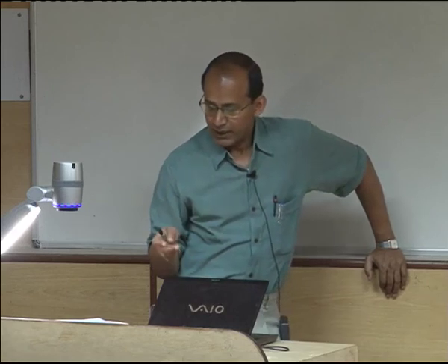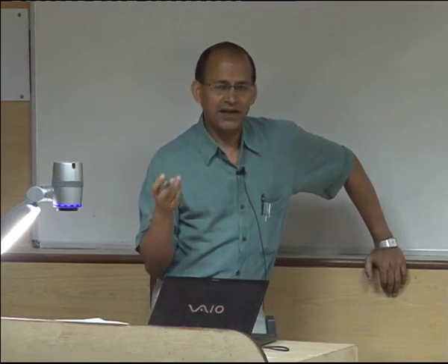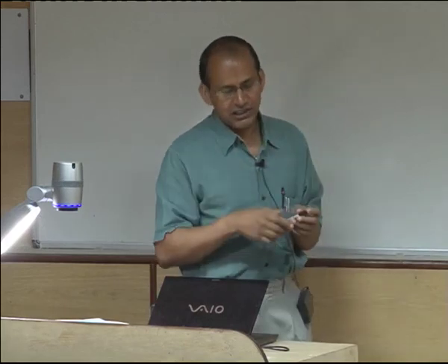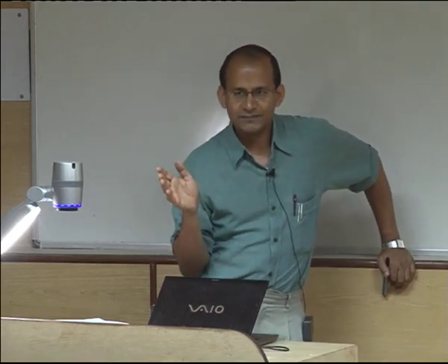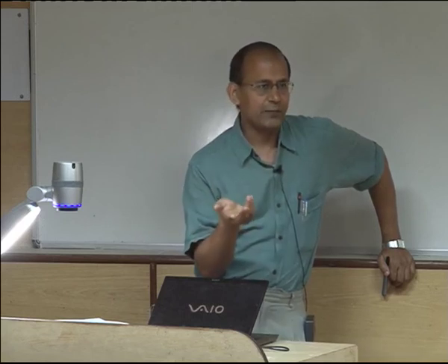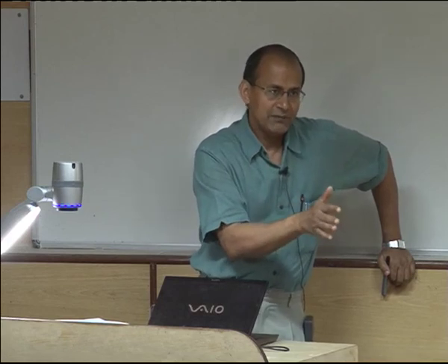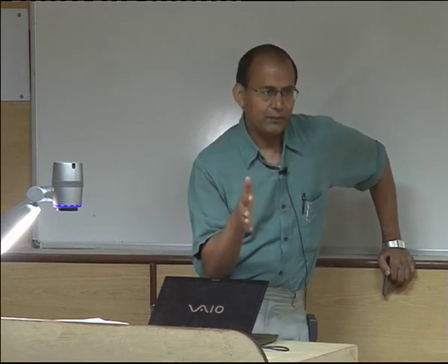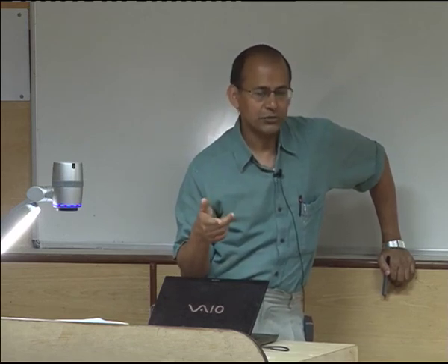Okay, and the induced draft fan, the ID fan, and the FD fan or the PA fan have different characteristics. Just now I showed you a video which talked about forward curved, radial and backward curved vanes, and what was told to you is backward curved vanes are industrially preferred, right? That was talked about in the context of centrifugal pumps, but it's also valid for centrifugal fans and blowers.